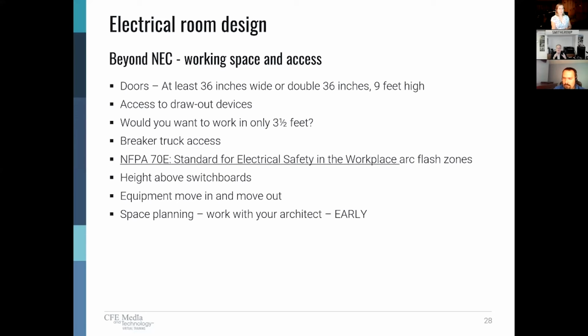Arc flash is a whole other topic, but arc flash basically calculates the amount of energy and then gives incident zones and defines the amount of PPE, or protective equipment, that you have to wear based on the zone and the incident energy in that zone. So the more space you have, the better for people who are either working or supervising people who are working within those zones.